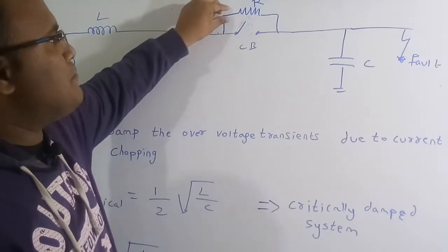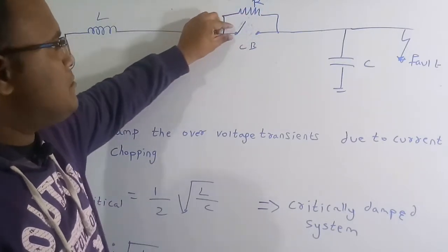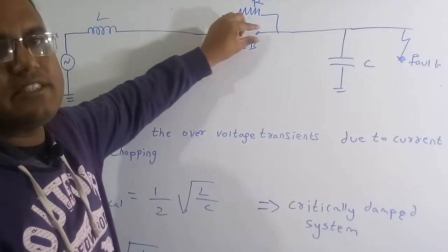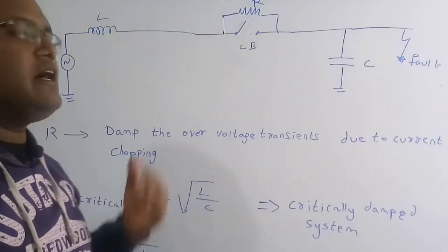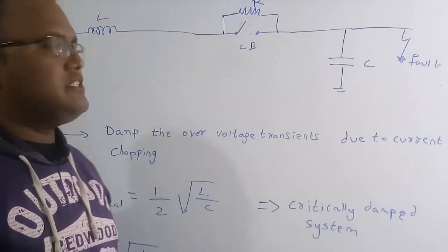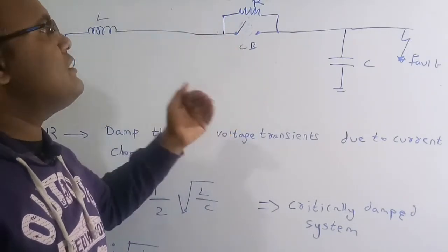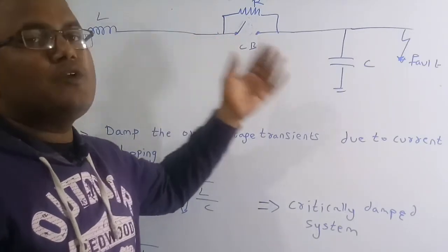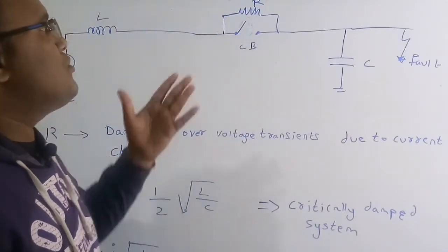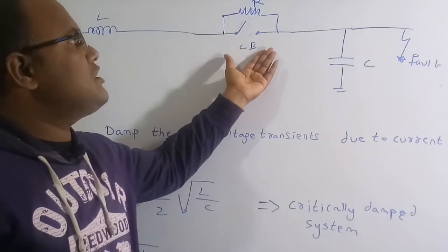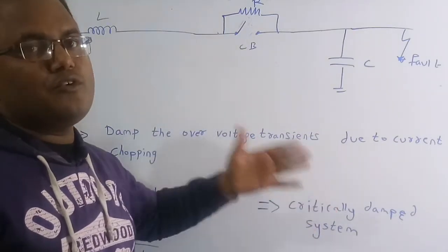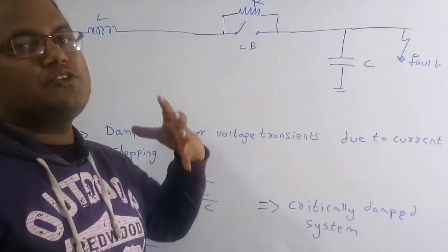Some amount of current can pass through this resistor, and also some amount of arc is going to pass through these contacts, because here it is going to act like a connector because of the huge amount of charges. But now because of this method, the restriking voltage needed to make a new arc is going to get reduced. So because of this resistor, the voltage across the contacts is going to reduce. Therefore this voltage is not even sufficient to make an arc.